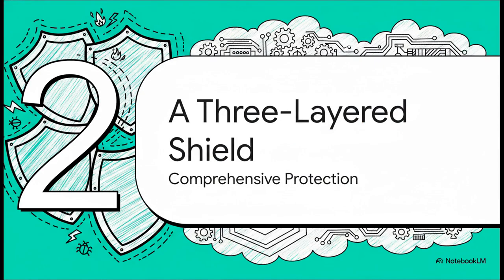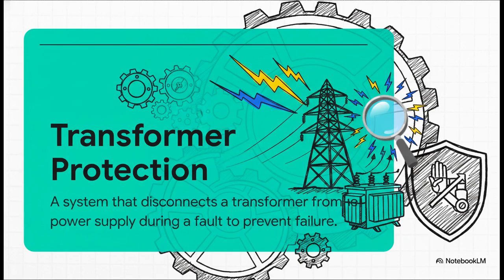So how do you fight all these different kinds of problems? Well, you can't just use one solution. Engineers have built a really comprehensive, multi-layered defense system. The best way to think about it is like a three-layered shield, with each layer designed to spot and stop a different kind of threat before it spells disaster. At its heart, this is what transformer protection is all about. It's not just one gadget, it's an entire system of devices working together. And they have one critical job: sense a fault the very instant it happens, and boom, disconnect that transformer from the grid. It's an automated, super high-speed guardian angel.